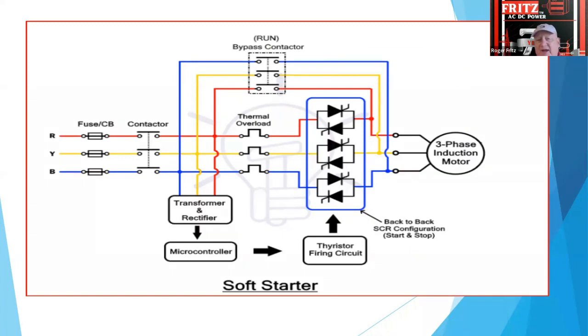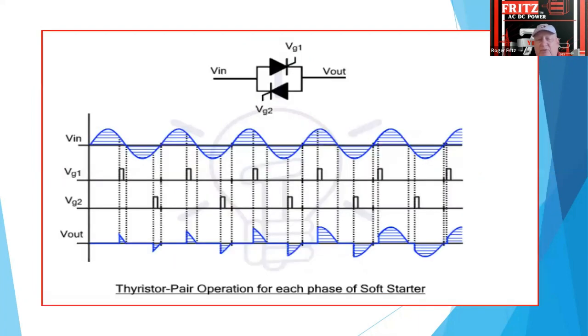So this is more of a circuit that is out there. You've got SCRs here driving the power to it, and then after it gets up and running, they have these bypass contactors. A lot of them today have built this contactor inside the units. Some still have an external run contactor on them when it's up to speed. Once it's up to speed, it doesn't really save any power in most cases, unless you go to the soft start, soft run type control.